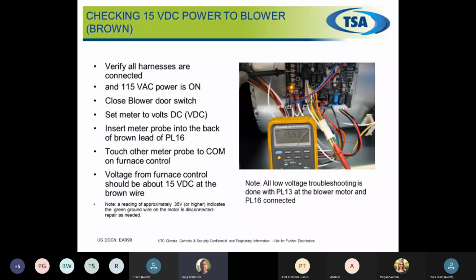So this motor here, standard in our 80s, 100s, our 60s, our 40s, we're going to be looking for 4 wires. We're going to be looking for our white and our black, which is standard 115 volts going to the motor at all times, no matter what. This one here will have a yellow and brown wire. Depending on the models, they have different plugins, but they're the same concept. Power going to the motor, power coming back from the motor to the board. Very easy to check.